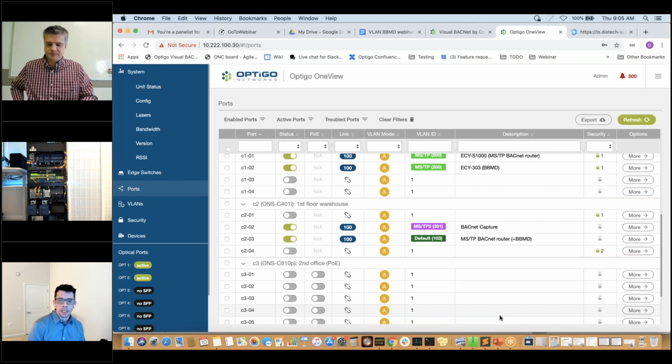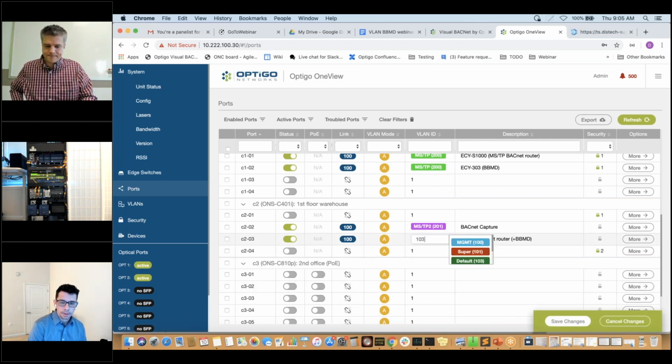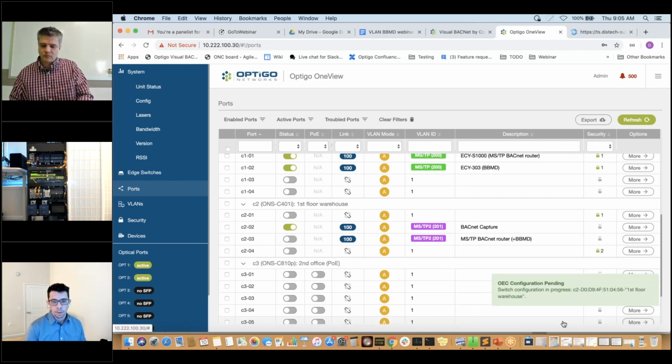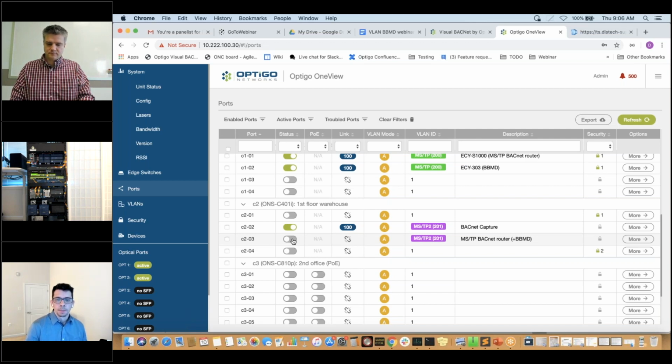Dave, can you put the BACnet router on 201 for me? Thank you. And so here we're moving everything up to a new VLAN, and we've segregated traffic. But what we're going to do now is say, well, we want to see that traffic come back. We've segregated them, but for some reason we do need them to talk. In fact, we needed them. So instead of getting rid of the VLANs for this instance, we're going to use a BBMD to bridge traffic across those VLANs. And you can see what happens to the traffic once we do that in the capture. So I'll bring it up on my side.